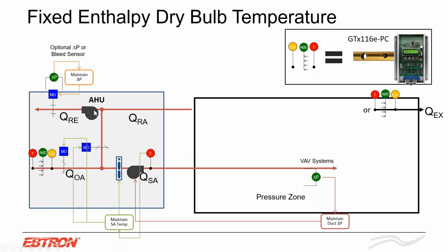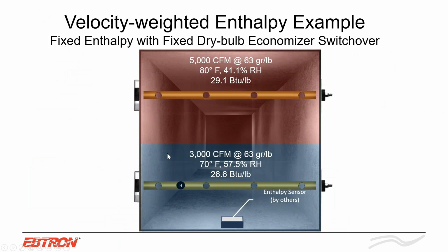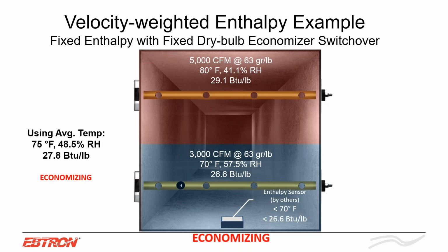Now, this is fixed enthalpy dry bulb temperature economizer strategy. Again, we can do whatever economizer strategy you need. Let's take a look at this. Again, it's kind of the same as the last strategy where we were doing fixed dry bulb. But if you look at the situation, if you were using an enthalpy sensor by others, it would be reading 26.6 BTUs per pound. And when you economize, you really want to be under 28 BTUs per pound.